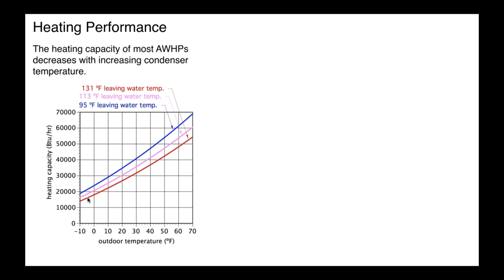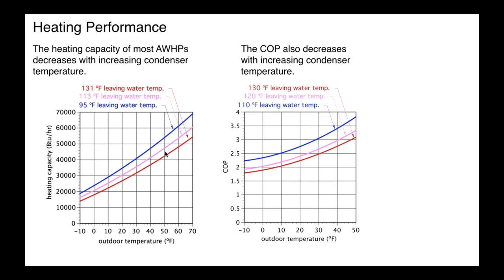Okay, so you can see here, if we can operate that heat pump with 95 degree Fahrenheit leaving temperature, that would be going into some type of very low temperature system, perhaps a radiant floor panel with close tube spacing in a well-insulated building, we're going to get this upper performance curve. But as we increase temperature, if we go up to 113 and eventually up to 131, you can see our capacity does drop off. So we need to build that effect into our performance simulation. And it's a similar story with coefficient of performance. The warmer we operate the hydronic system, the higher the water temperature that we're requiring, the lower the coefficient of performance. And the coefficient of performance is essentially its output divided by input.